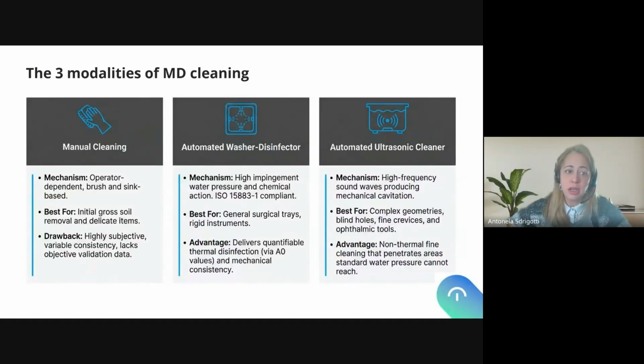So with the manual cleaning, the mechanism behind is operator dependent, brush and sink based. It is best for initial gross soil removal and delicate items. The drawback of manual cleaning is that it is highly subjective, variable consistency, and lacks objective validation data. On the other hand, we have automated washer disinfector. The mechanism is high impingement water pressure and chemical action, and should be ISO 15883 Part 1 compliant.